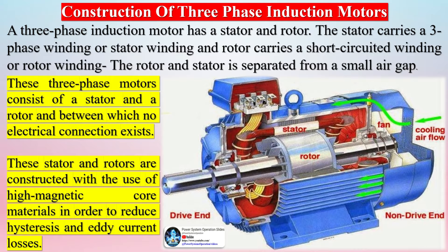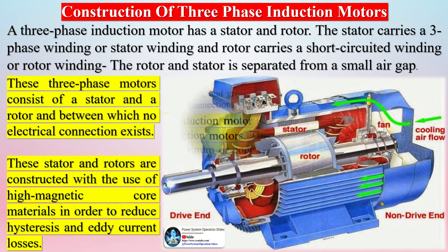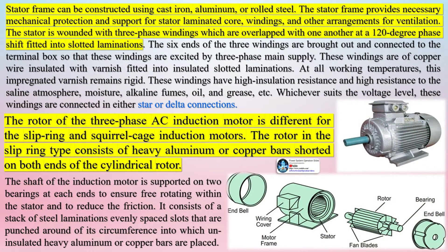The stator frame can be constructed using cast iron, aluminum, or rolled steel, providing necessary mechanical protection and support for the stator laminated core, windings, and ventilation arrangements. The stator is wound with three-phase windings overlapped with one another at a 120-degree phase shift, fitted into slotted laminations. The six ends of the three windings are brought out and connected to the terminal box so that these windings are excited by the three-phase main supply. These windings are of copper wire insulated with varnish, fitted into insulated slotted laminations.